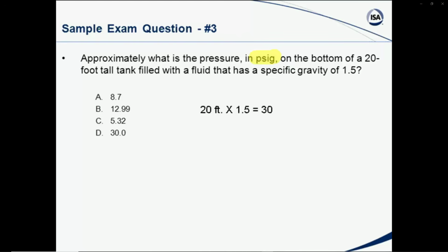I could just jump down and say, well, that's easy. The answer is 30. Watch your units, units, units. What I have at this location is 30 feet. I don't have a situation of 30 feet of water. I've converted that to the equivalent head of water. I have 30 feet of water. So now, what do I have to do? I want to get it to what units, PSI? I will have to say 30 feet of water.